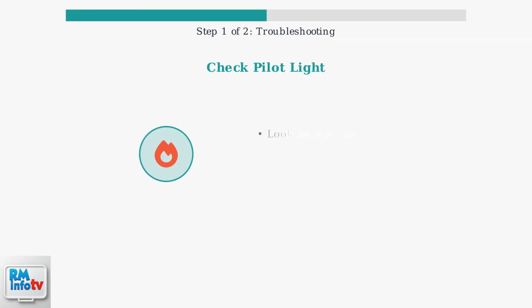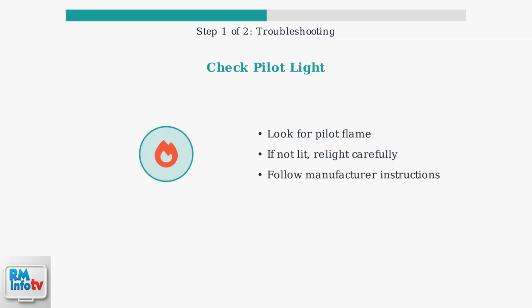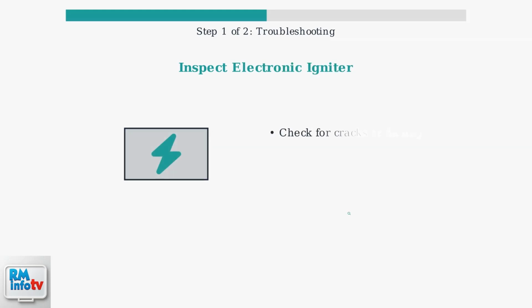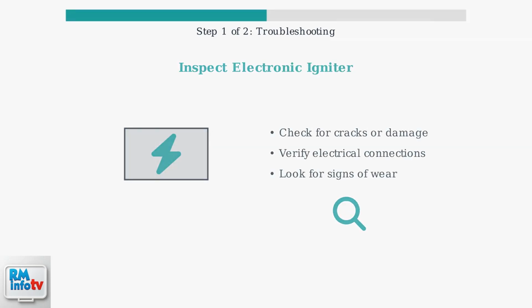Start your troubleshooting by checking the pilot light if your model has one. If the pilot light is not lit, follow the manufacturer's instructions to relight it safely. For electronic ignition systems, carefully inspect the igniter for any visible damage such as cracks or wear. Also check that all electrical connections are secure.